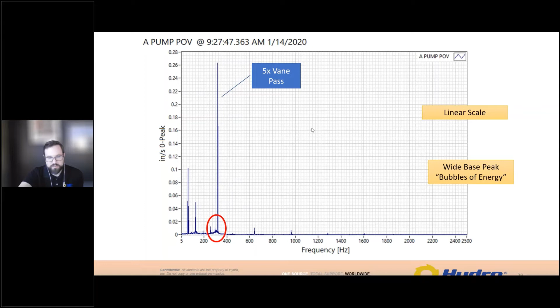If I look down here, I see this bubble, okay? It's much easier to see this in logarithmic scale. This is linear scale right now. If I switch to logarithmic scale, you can see this upside down V shape. This very wide base oftentimes indicates a natural frequency right there, and right at the tip of this V is oftentimes going to be a natural frequency. And you can see that this vane pass peak is not dead on that V, it's interacting with it and you're getting some amplification.